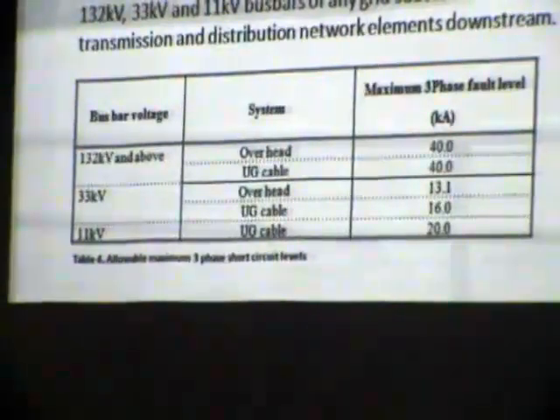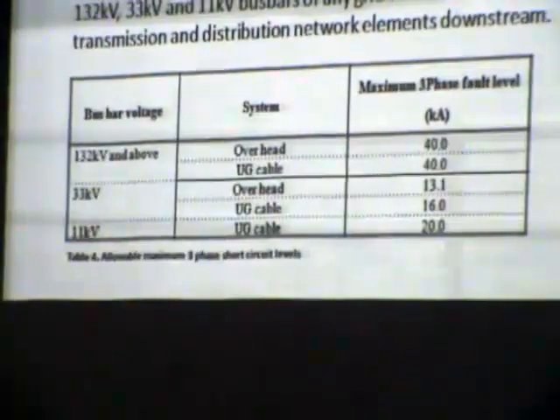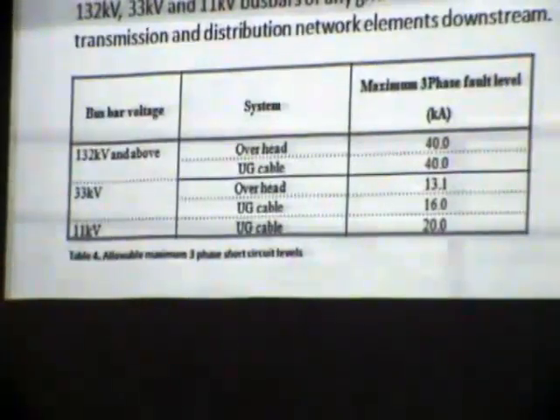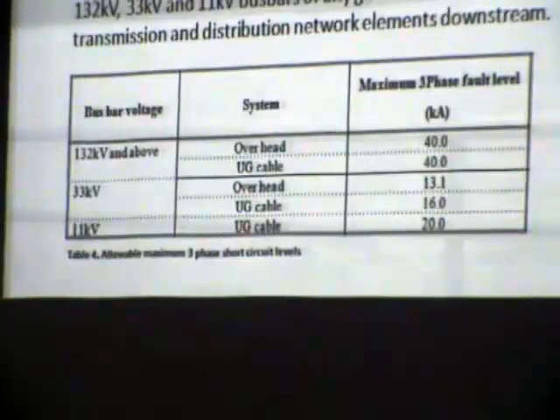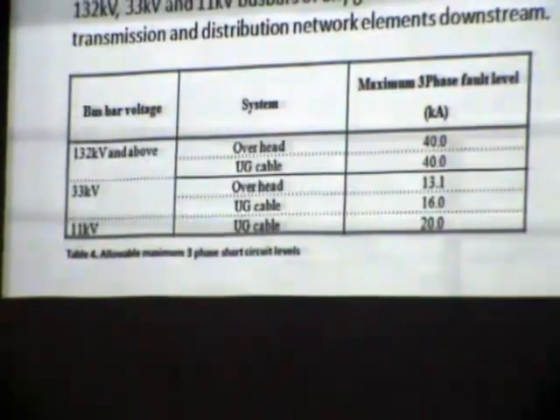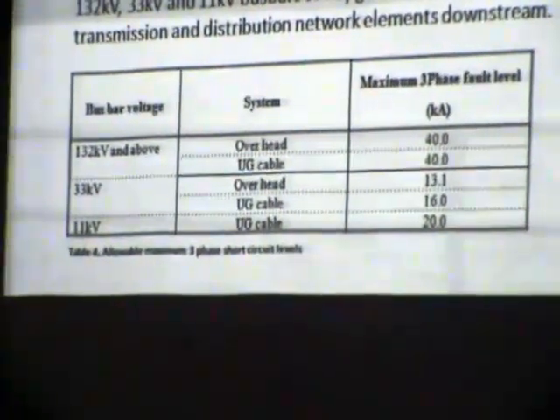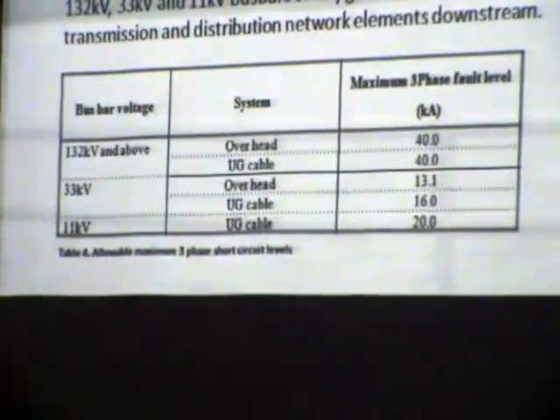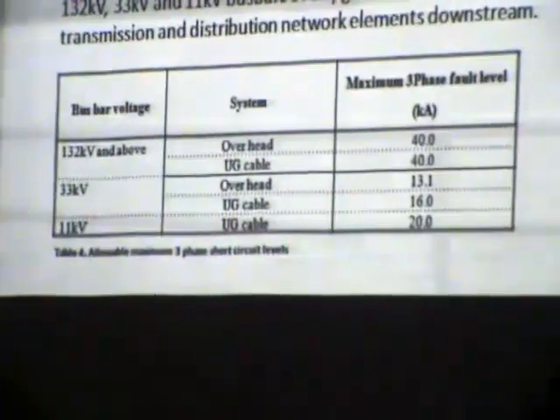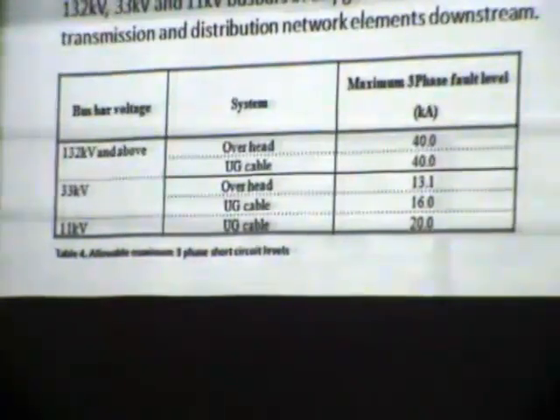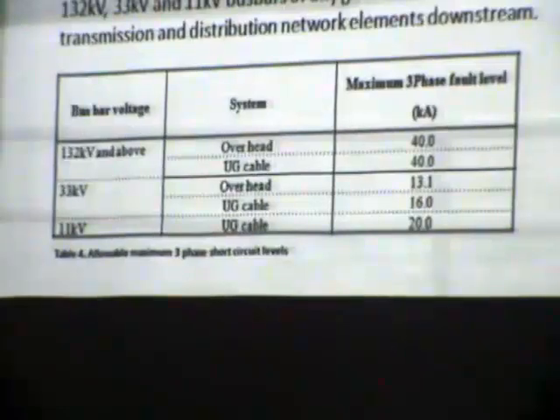For that we impose a three-phase short circuit at every bus bar and calculate the maximum three-phase current at each and every bus bar. That is every 132, 33 and 11 kV bus bar, and check whether that limit is exceeded or not. Consider that a 33 overhead grid substation has a 13.1 kA maximum short circuit level, but if it is exceeded at the 33 grid substation level, then all the downstream equipment has to be replaced. Otherwise, they get damaged in a fault. It is not possible to replace all the downstream equipment, so we have to plan our transmission network to avoid exceeding that maximum three-phase short circuit level.